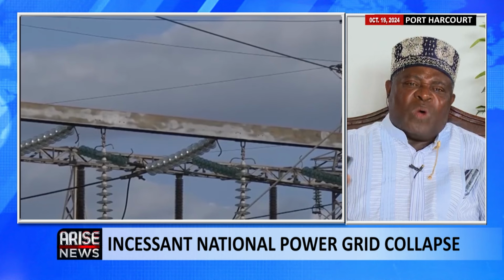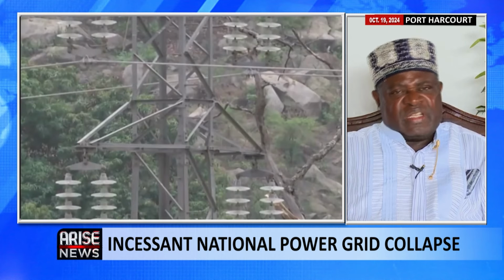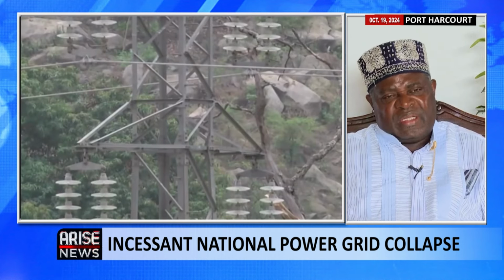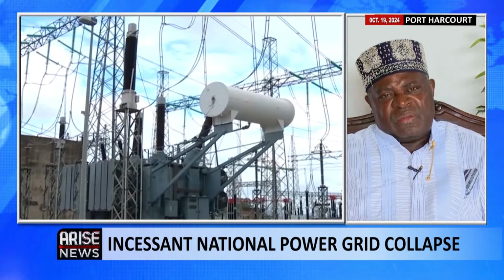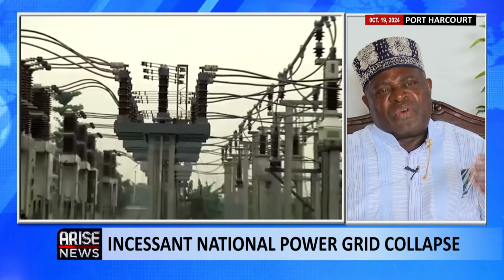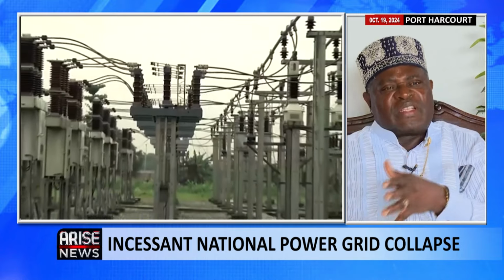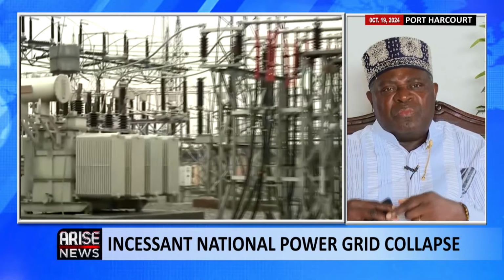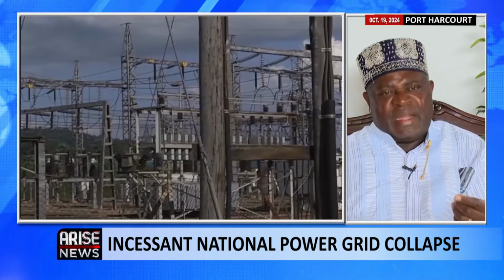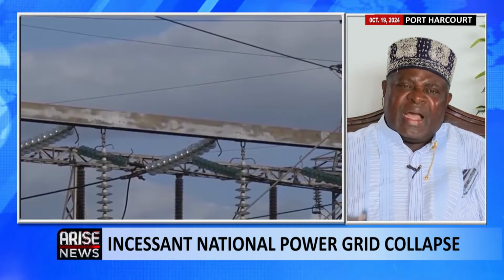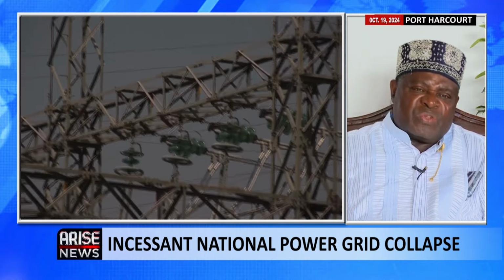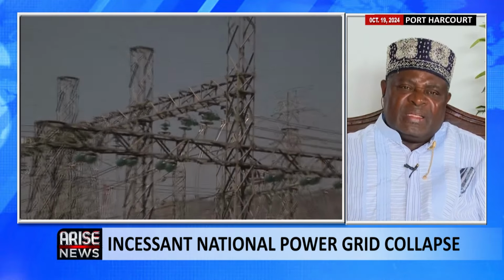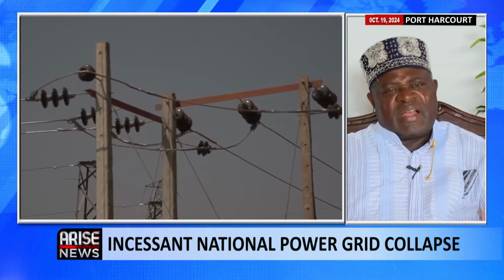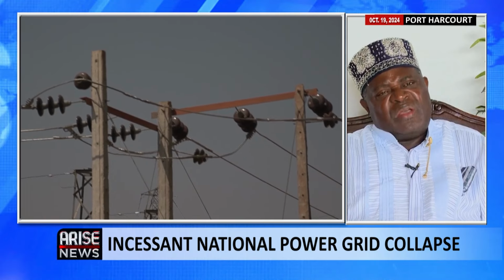Even if we had just 1,000 megawatts of spinning reserve per day, we wouldn't have these collapses, because the collapses arise from the challenges of overstressing the line through different dynamics in the power equation. Most of these issues are addressed when you have enough reserve to intervene at different levels. But we don't have that.